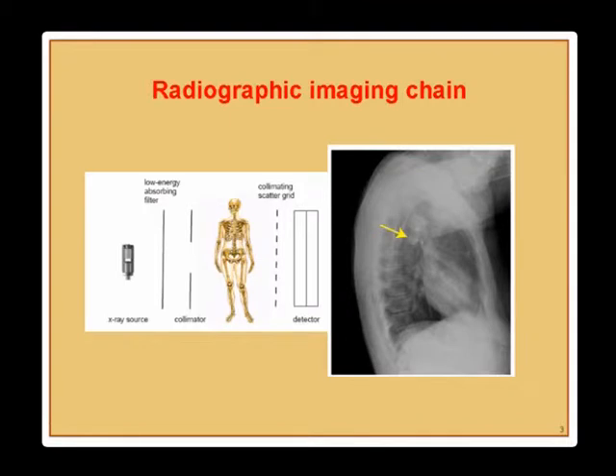Typically a radiographic imaging chain starts with an x-ray source, then a low-energy absorbing filter, because low energies basically just add to patient dose without adding image information. So we use aluminum filters to reduce patient dose. Then there is collimation, an anti-scatter grid, and then a detector. People are used to screen-film systems in radiology, which are the traditional systems where you have a scintillator that converts x-ray photons to light photons, which then expose film.